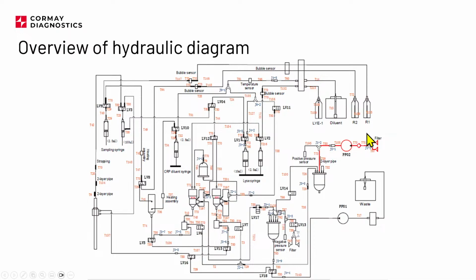One more thing which can surprise you is, since we use latex particles as a CRP reagent, the analyzer also needs a way to mix those latex particles periodically in the bottle. So it will simply use the up and down movement of this syringe, and this will push and pull some liquid through those tubes up and down a few times, and this will mix the whole volume of the bottle correctly, and there is no risk of any sedimentation of those latex particles to the bottom. So this is how it's done. To remove the liquid from here is pretty straightforward. We're just going through a few of those valves and waste, and here we go.